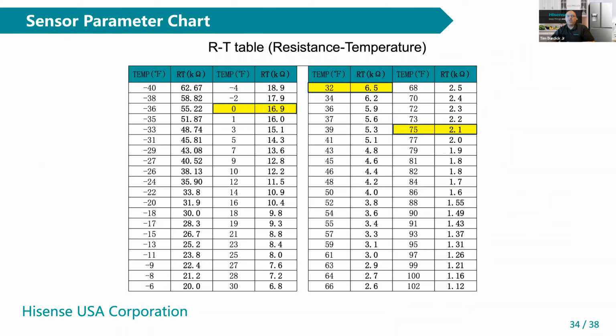What do those temperatures look like and what resistances correspond to them? Here's the chart. I've highlighted a couple of key temperatures we should always get an idea of for each manufacturer. For Hisense, here they are: room temperature about 75 degrees, and I'm looking for a resistance of 2.1 K ohms.